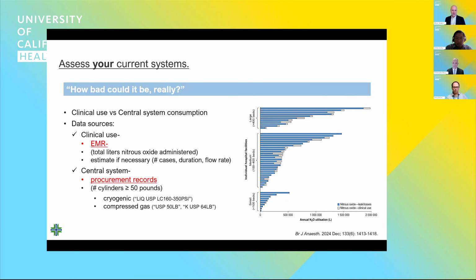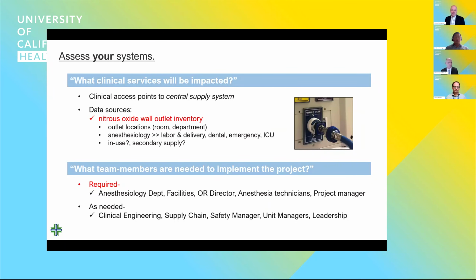You compare that against the central system consumption, which we get from procurement records, really honing in on data that is best acquired from your medical gas vendors directly, really looking at the number of cylinders containing more than 50 pounds of nitrous. Those are the ones that are attached to the central system. There are other cylinders containing nitrous that are used throughout the hospital. You don't really want to include those in this assessment of central system efficiency because they're not used in the central system.